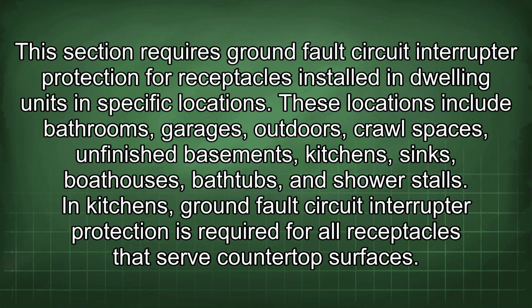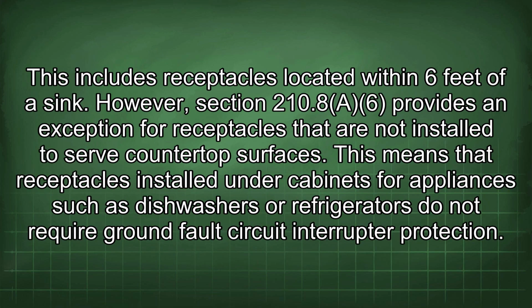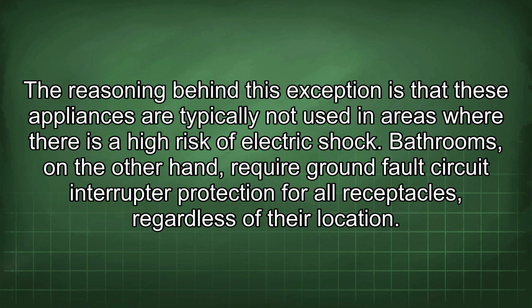In kitchens, ground fault circuit interrupter protection is required for all receptacles that serve countertop surfaces. This includes receptacles located within 6 feet of a sink. However, Section 210.8(A)(6) provides an exception for receptacles that are not installed to serve countertop surfaces. This means that receptacles installed under cabinets for appliances such as dishwashers or refrigerators do not require ground fault circuit interrupter protection. The reasoning behind this exception is that these appliances are typically not used in areas where there is a high risk of electric shock.